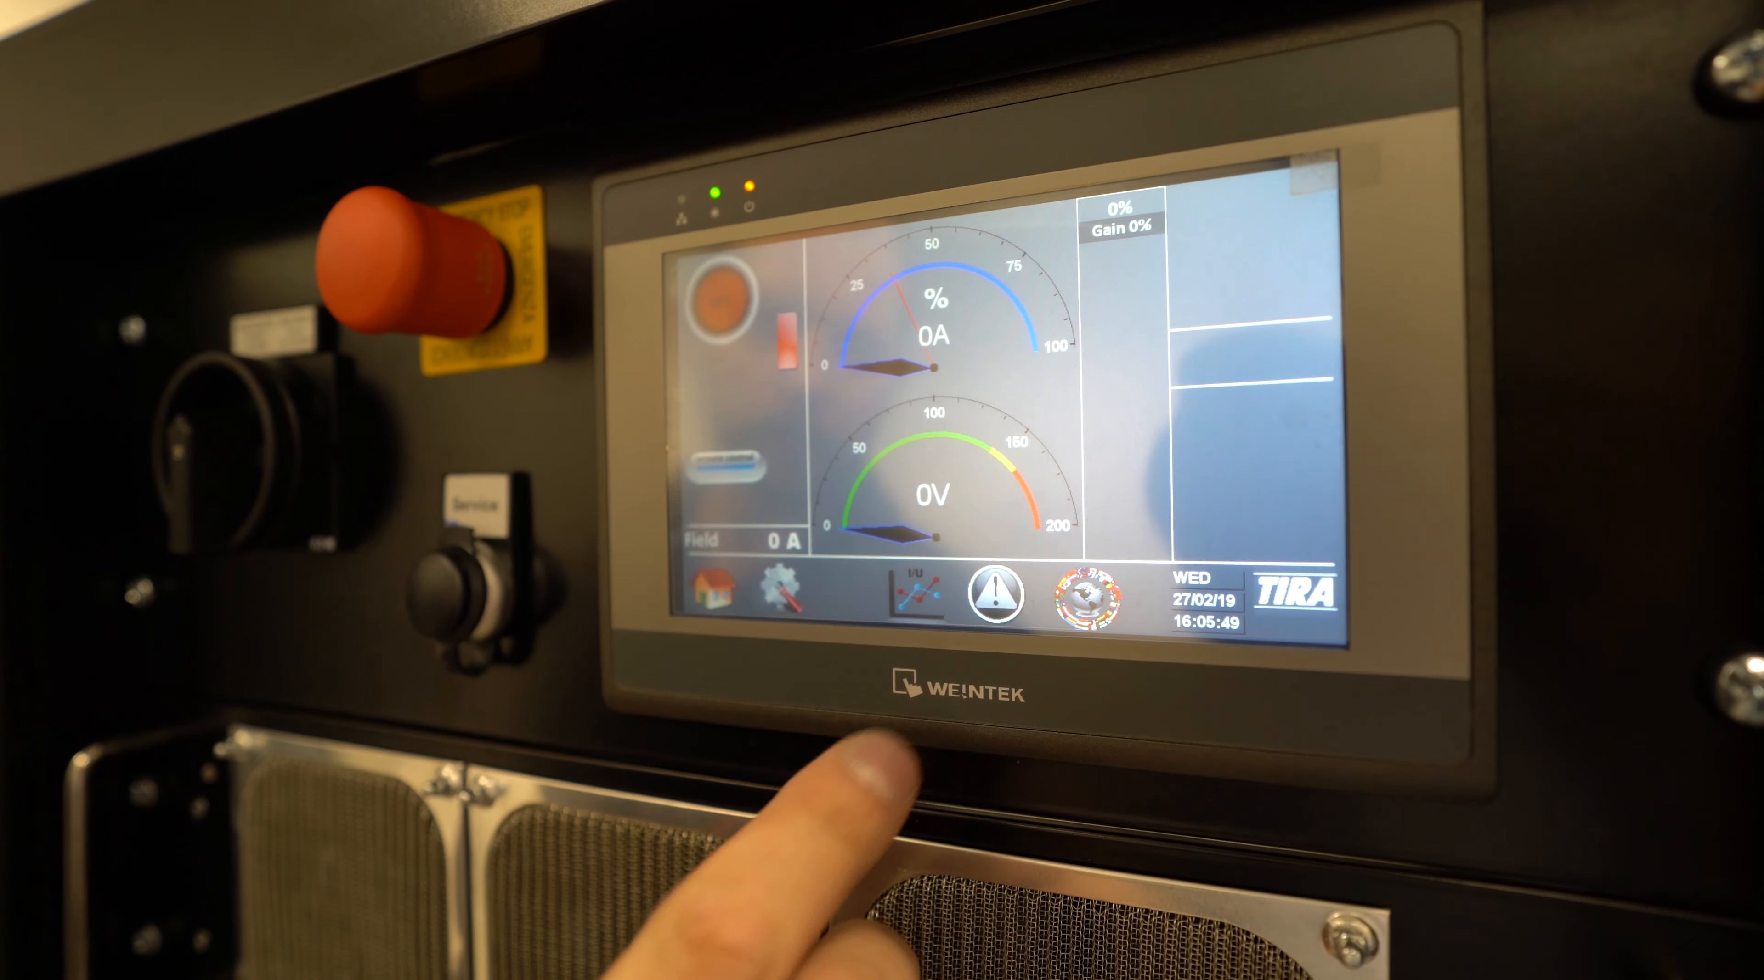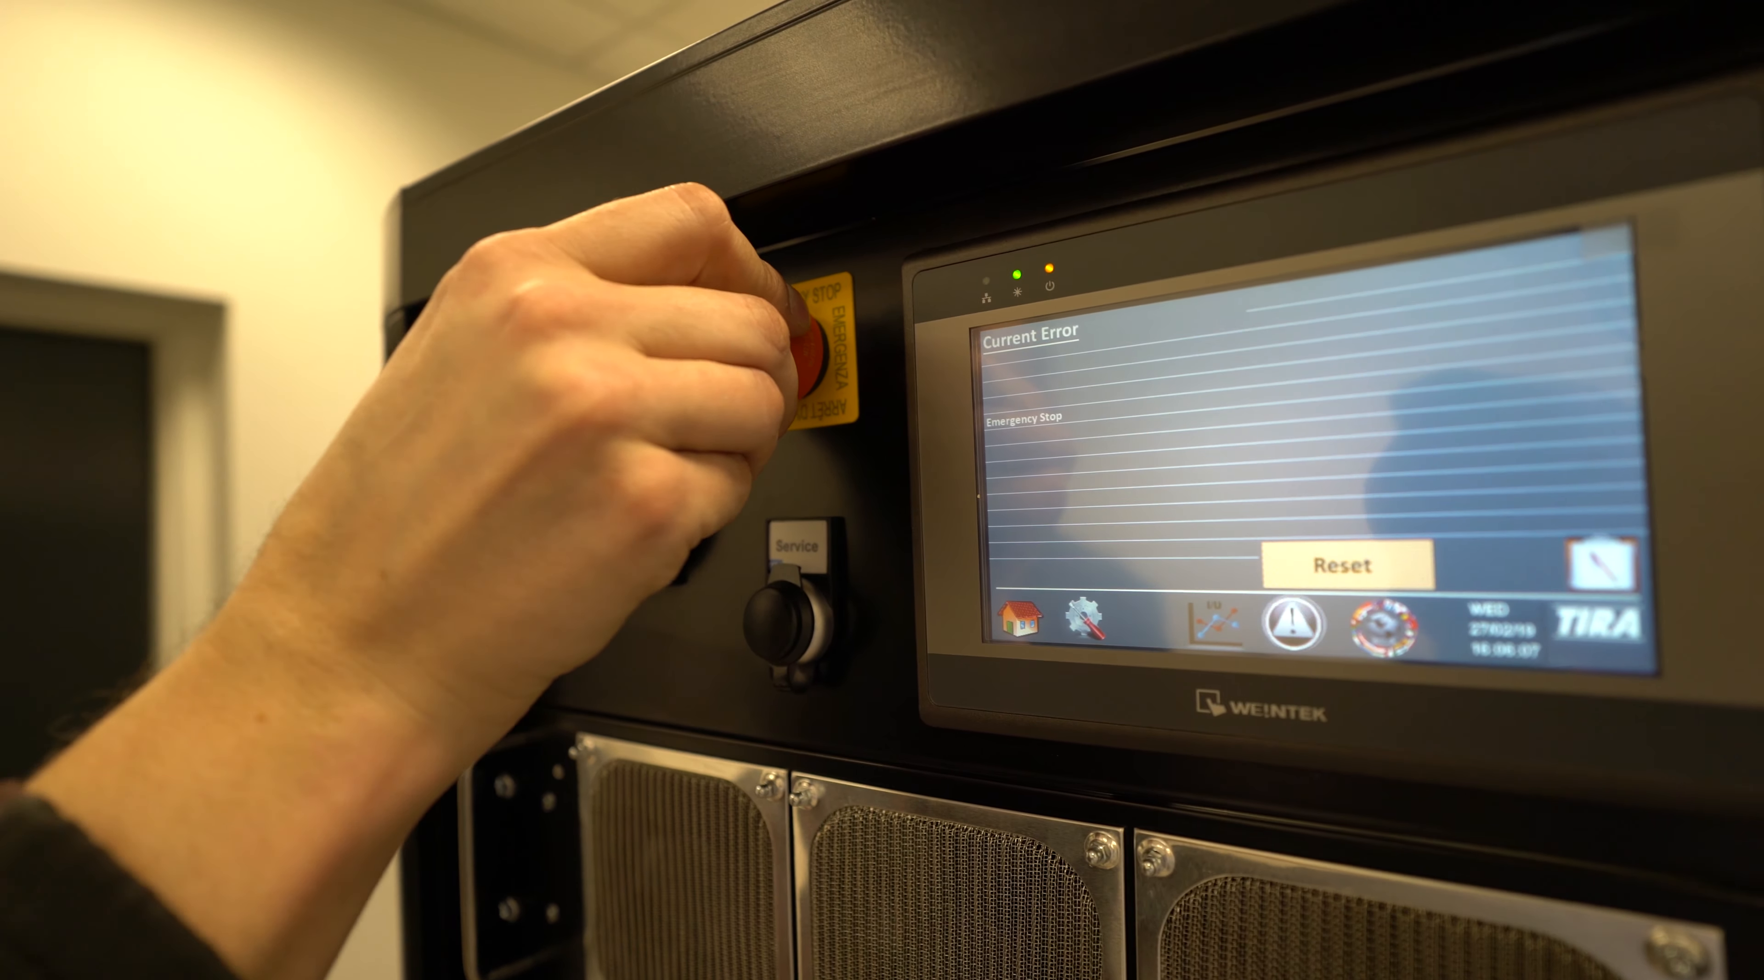So if you click on there, you'll see it'll pull up our list of current errors. The error that we have right now is emergency stop. That means that the emergency stop button here right next to the display is set. If you want to unset that, go ahead and pull, and then to reset the alarm code, press and hold reset for about two seconds and let it go. Now you can see that our emergency stop error has gone away.